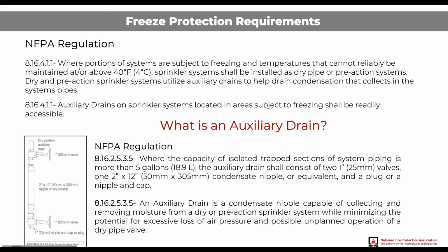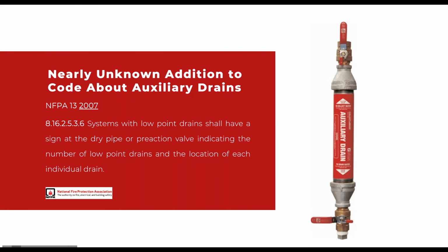The idea behind a dry system is the majority of the system is pitched back to supply, but in the areas that you would have trapped sections, you have to have these auxiliary drains to collect any accumulation of moisture. And again, like I said, very simple. Two valves, a reducer, and a 1 foot piece of 2-inch pipe, and then periodically someone goes along. First, of course, before there's any type of freezing condition, someone would go along and drain out any accumulated moisture out of these units.